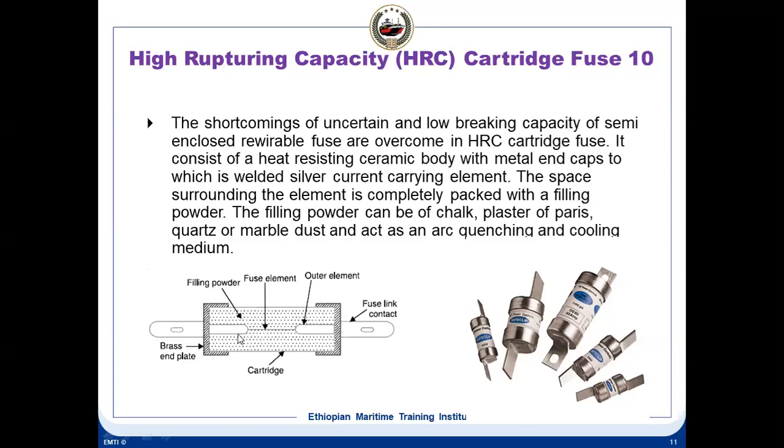So what happens when the high current flows, this will melt off, but because of the inductive current, there can be an arc through this. And the current can still flow. There is an arc here and it can go to your equipment which is to be protected.